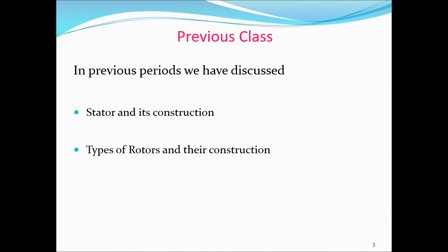So if you consider the salient pole rotor, it is used for low and medium speed machines. The rotor poles are made with steel laminations, and it is fixed to the rotor. The rotor poles contain slots, and the slots contain the damper winding. The damper windings are short circuited at both end rings, as we showed in the last class. Figures will also be shown. Why is the damper winding used? The damper winding is to prevent the hunting.